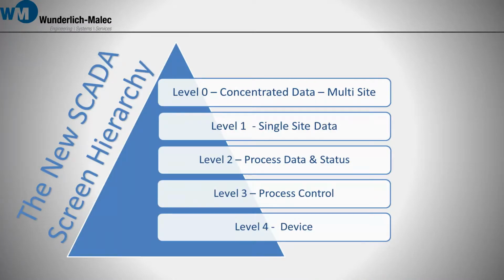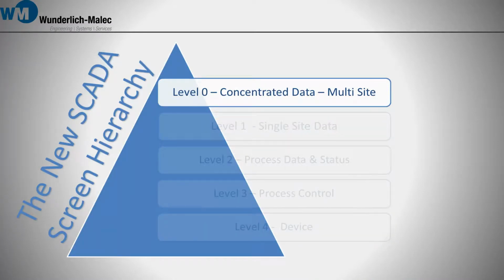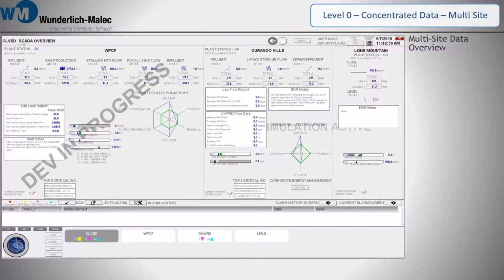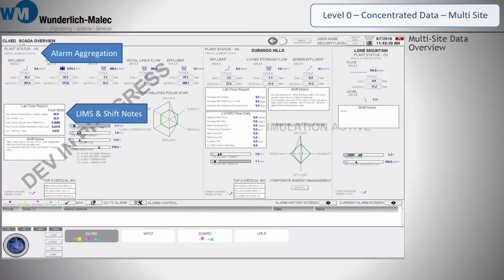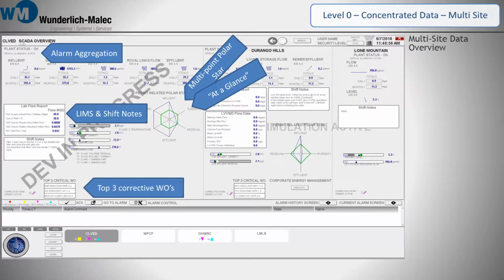This is the new SCADA screen hierarchy. We'll start at level 0, where we show operations a clear look at how each site is performing. It presents aggregate data of multiple sites. Is there a critical alarm active at the site? We list the pertinent alarms and shift notes. The permit-related polar star gives an at-a-glance look at how closely the process relates to the set point. And finally, what are the top 3 corrective work orders?